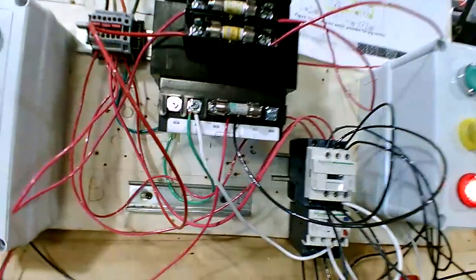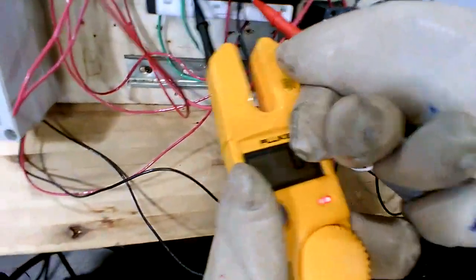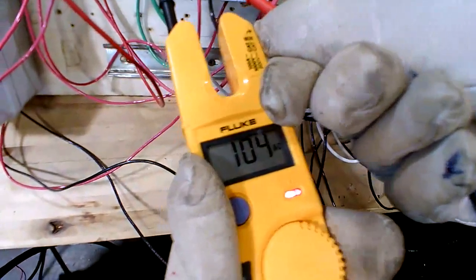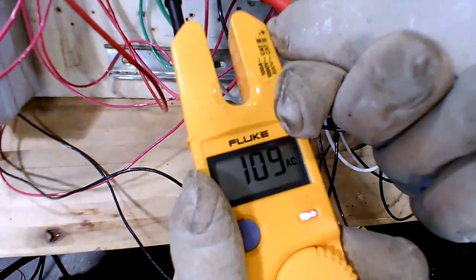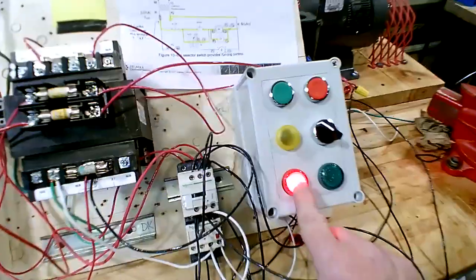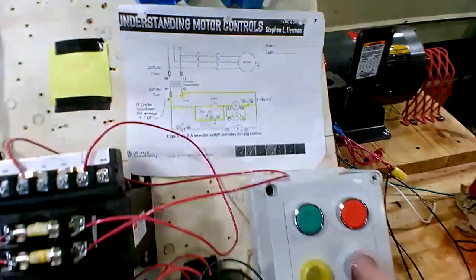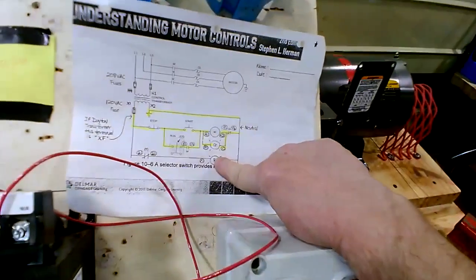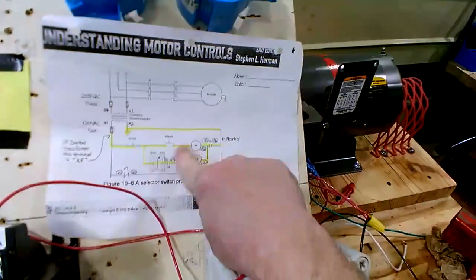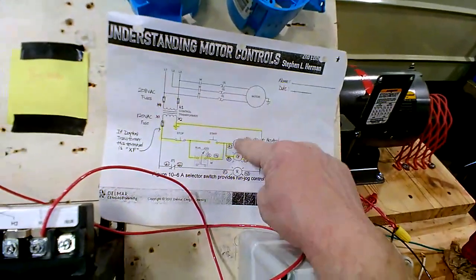So put your meter on there, Benjamin, and show everybody. He's got 109, close to 110 volt, that's fine. So we know we've got control power. And by that red light being on right there, that means you've got power all the way to there. So we've got a hole in here somewhere between the start and the coil.